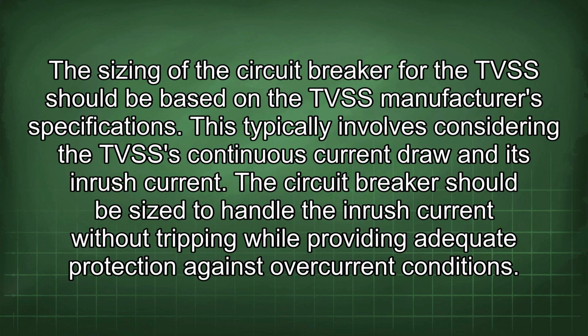The sizing of the circuit breaker for the TVSS should be based on the TVSS manufacturer's specifications. This typically involves considering the TVSS's continuous current draw and its inrush current. The circuit breaker should be sized to handle the inrush current without tripping while providing adequate protection against overcurrent conditions.